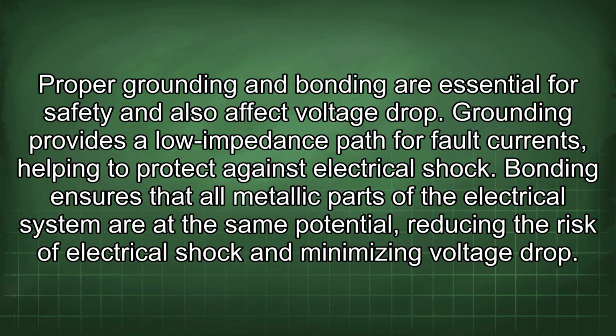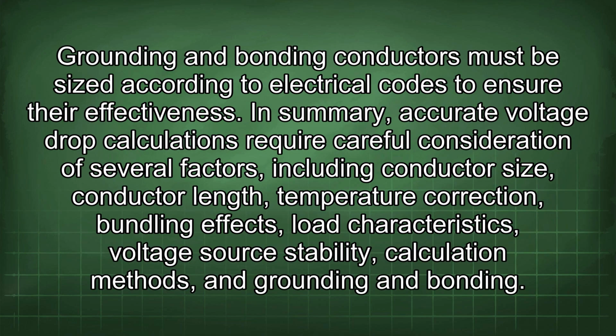Grounding provides a low impedance path for fault currents, helping to protect against electrical shock. Bonding ensures that all metallic parts of the electrical system are at the same potential, reducing the risk of electrical shock and minimizing voltage drop. Grounding and bonding conductors must be sized according to electrical codes to ensure their effectiveness.